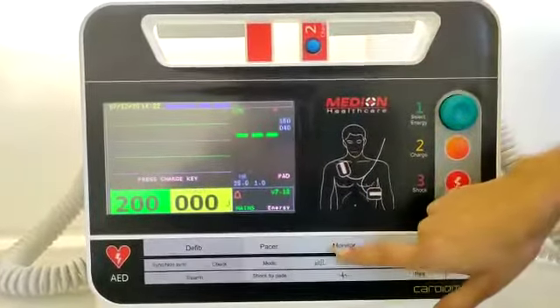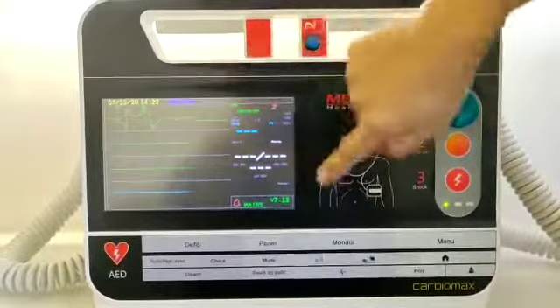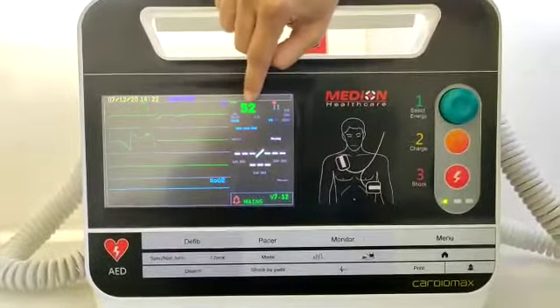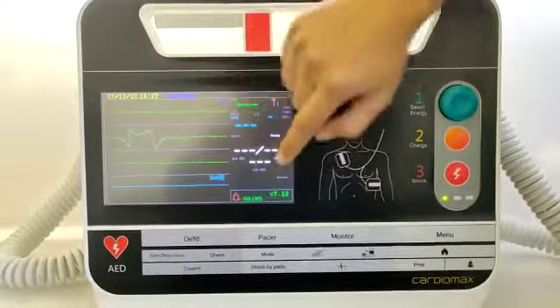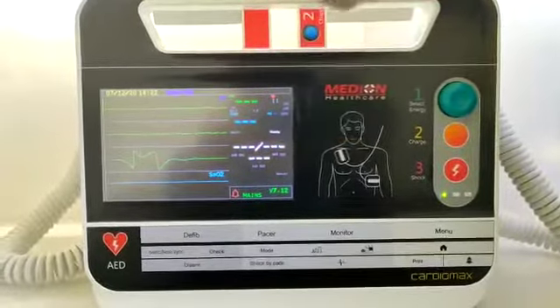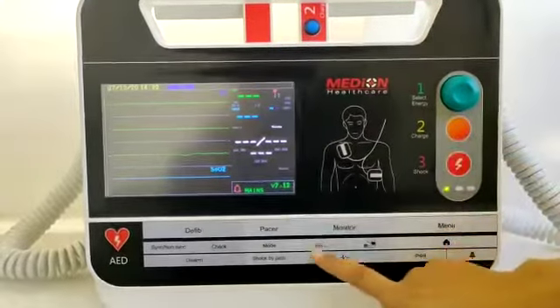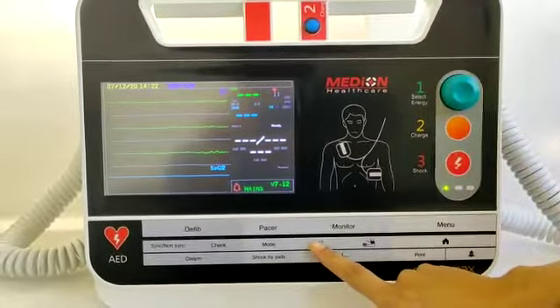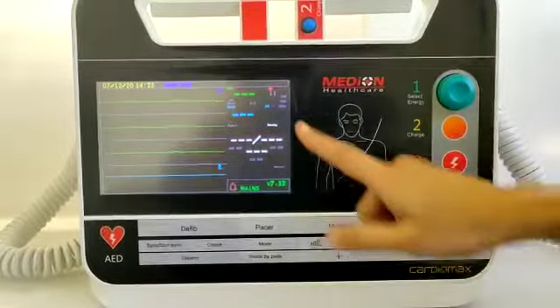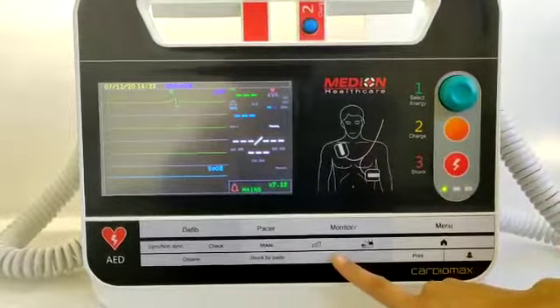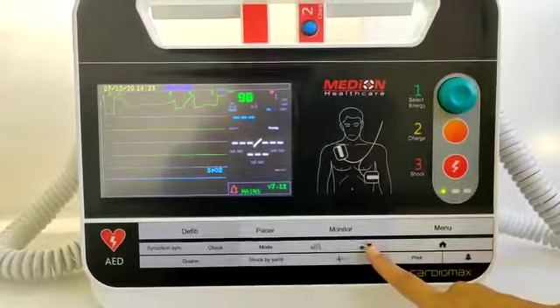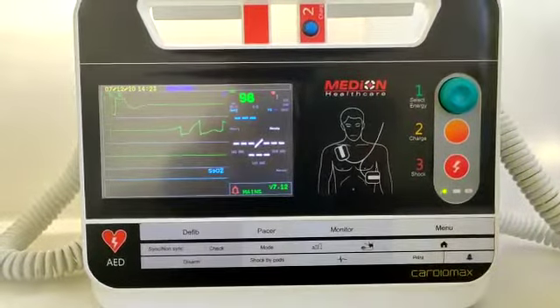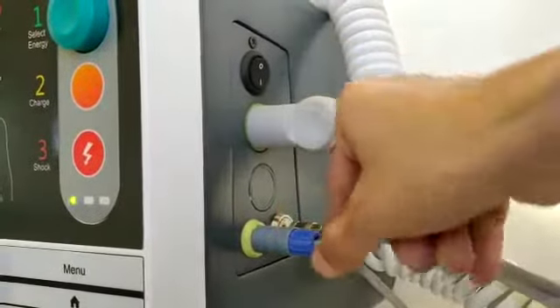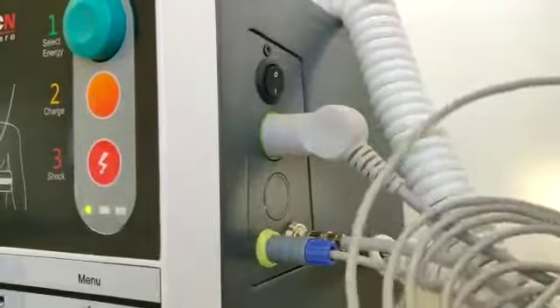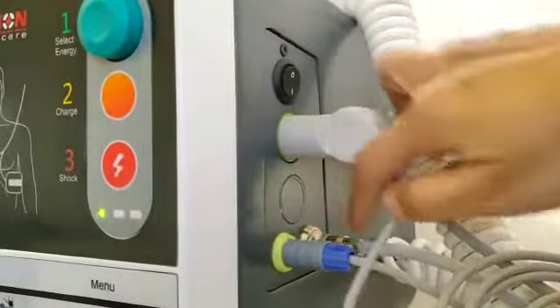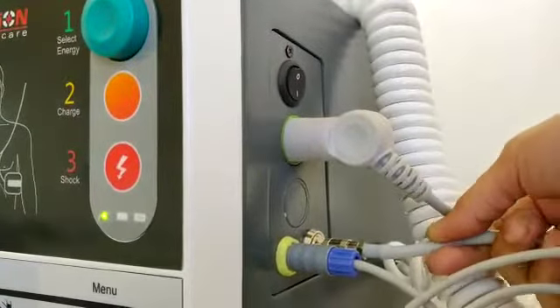Next is the monitor mode. In monitor mode, this is the window. Here ECG will be displayed. This is the SpO2, and it will display NIBP. To adjust the gain of the waveform, the user can use this feature. The leads can be changed from here, and this is to start the NIBP. Here the SpO2 probe is connected, this one. Here the NIBP tube is connected, and this is for the ECG.